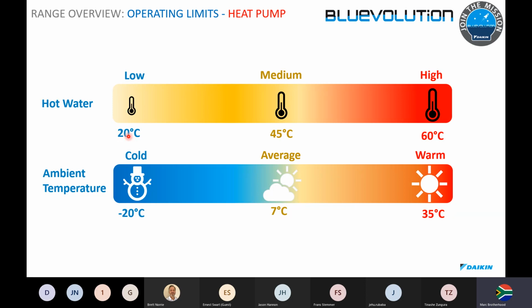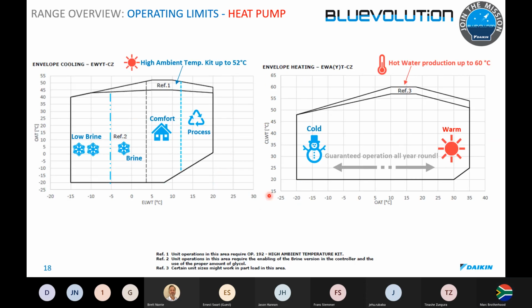The coldest water we can generate for you is 20, right up to 60 degrees, which is really hot. That's sort of your geyser temperature. Most geysers are set at around 55. However, we can generate up to 60 degree water for you. And here we will still be able to condense and provide this service up to 35 degree outdoor temperature and down to minus 20 outdoors. And hot water production is pretty much guaranteed all year round within these outdoor air temperature operating envelopes. So if you want to use this as a heat pump for hot water generation, being an inverter, it's very efficient on your coefficient of performance.